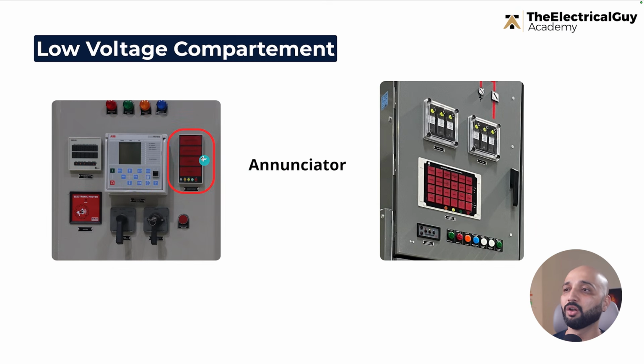Then you will also find annunciators. These are a few examples; you can see we have one on the left, one on the right. Again, there is no standard here. You can choose what type of window you want. The one red portion is what we call a window, and each window can have a separate indication of abnormal conditions. It can be 3 or 4 windows or up to 50, 60 windows, depending on what application you are using and what kind of indications you want. Now, a very common question comes up: what is the difference between indication lamps and annunciators?